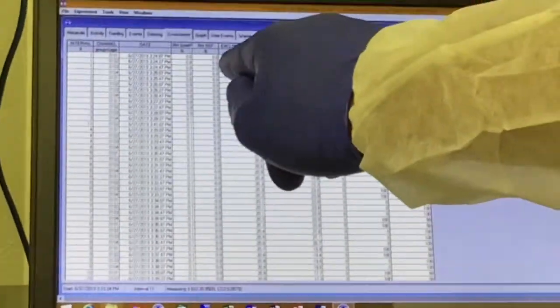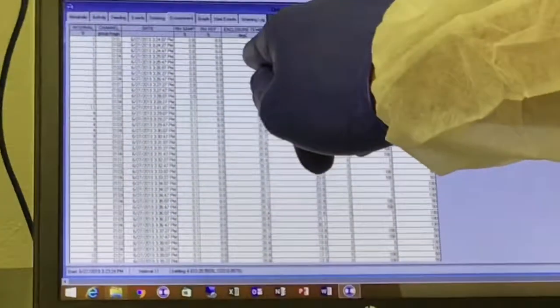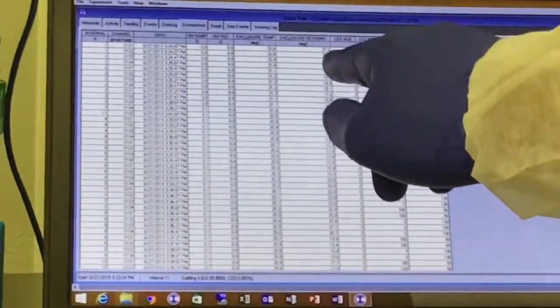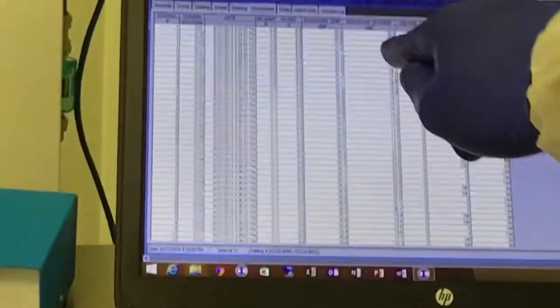What to look at is the enclosure temperature, where it's at, and the set point. It's set at 21.6 but it's at 20.6, so the heat turns on. It should go up, but in between the set point came down, so it should still try to go up. Then the set point went up, so it's just trying to keep up.